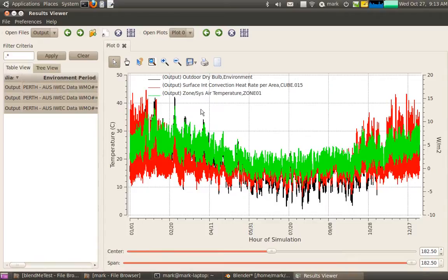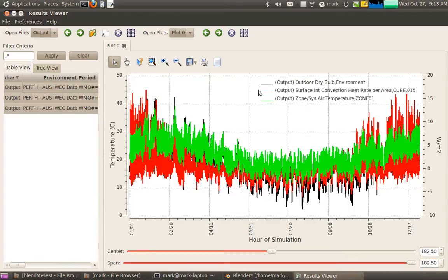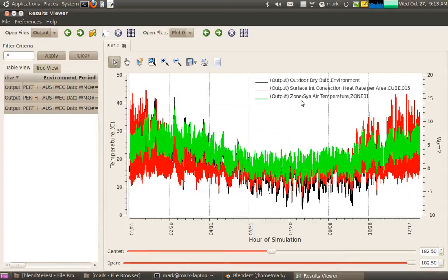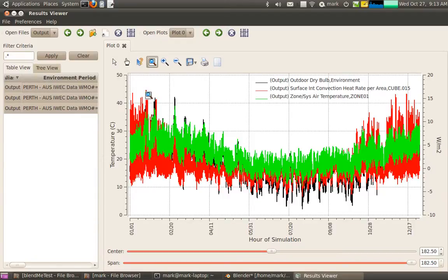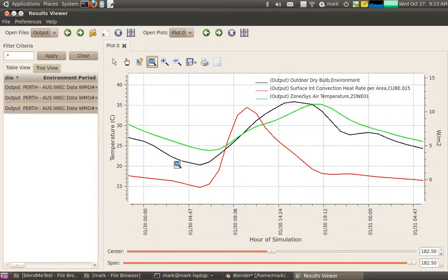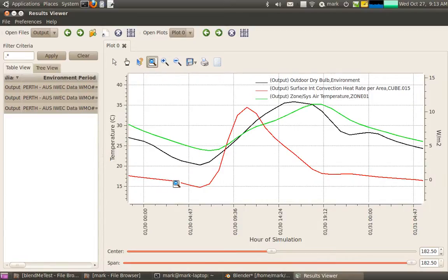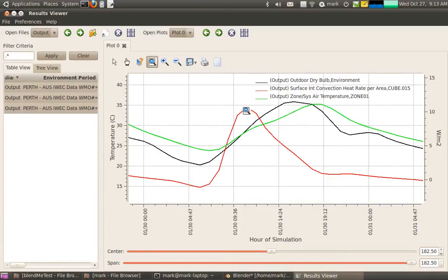I've got zone air temperatures, surface convection heat rate per meter squared, and outdoor dry bulb temperature. So if I actually just zoom into a typical summer's day, let's say around here, you can actually see there's the surface heat transfer of the eastern facing wall is getting hotter in the morning and dropping off as it gets shaded in the afternoon.